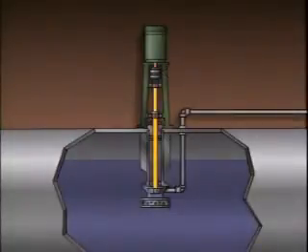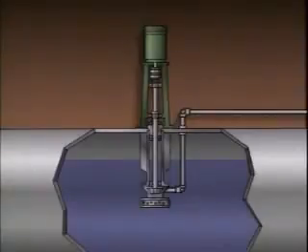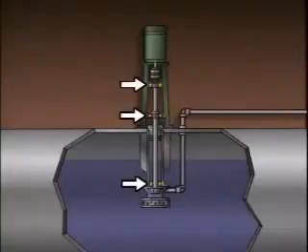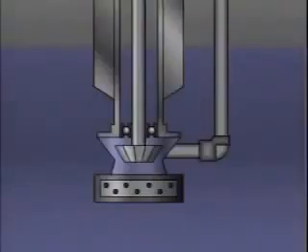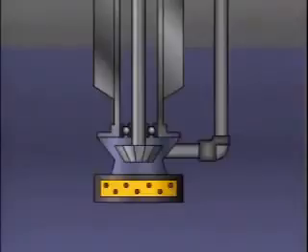This pump shaft is much longer than those found on most other centrifugal pumps. On any pump with a long shaft, it's important to keep the shaft in its correct position so that the pump will operate properly. Several bearings are used to keep the shaft properly aligned. On this pump, there is no suction piping. Instead, the suction of the pump is submerged in the liquid being pumped. The suction is covered by a strainer, which prevents trash or debris from clogging the pump and causing excessive wear.